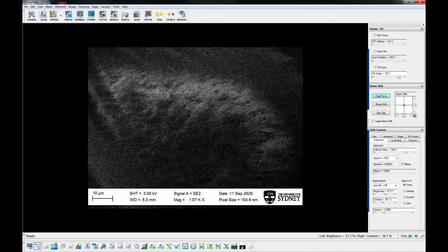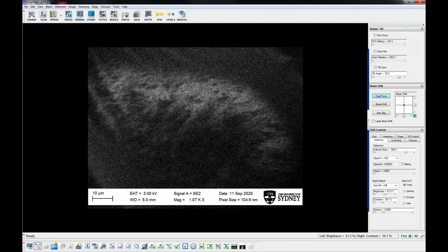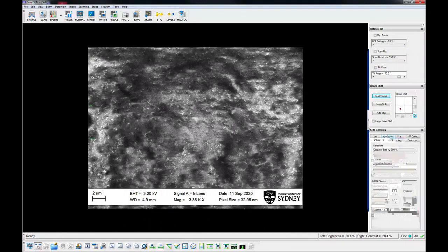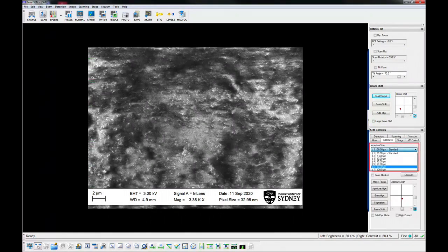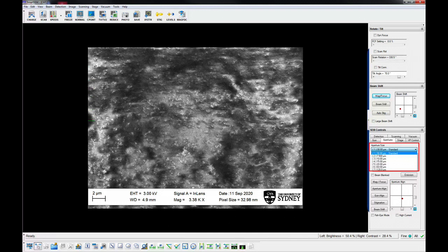Refocus and begin imaging using your desired detector. The SEM has a multi-hole aperture with sizes ranging from 7.5 microns to 120 microns. Increasing the aperture size increases the beam current. There is no useful improvement in resolution for apertures less than 30 microns, but you may need these sizes to control charging or specimen damage.